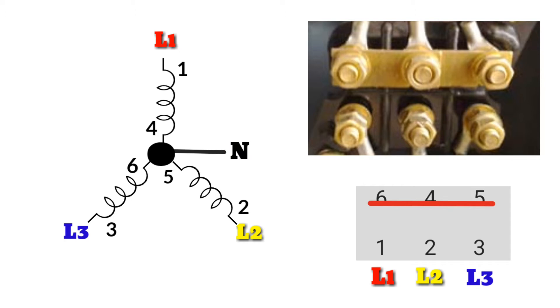As the star connection provides a low voltage across each winding, the current will be less. For this reason, an induction motor is started with star connection to reduce the starting current by reducing the voltage across the windings.